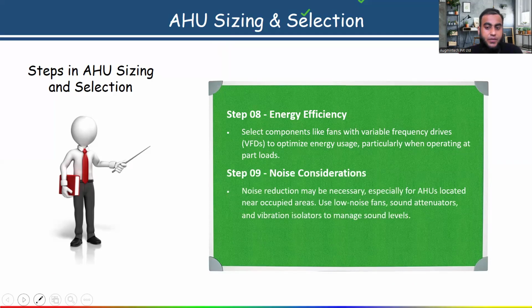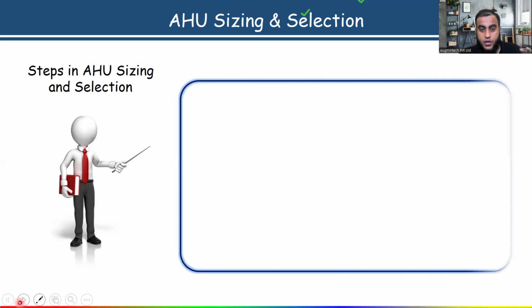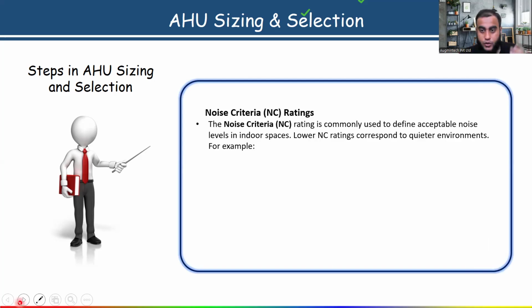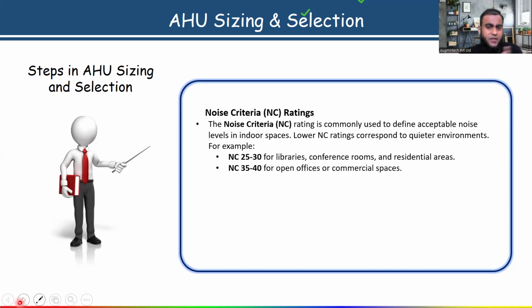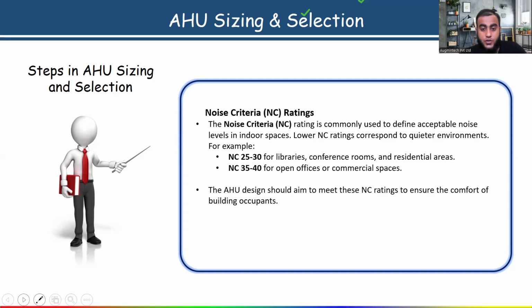Noise reduction may be necessary, especially for an AHU located near occupied areas. So use a low noise fan, sound attenuator, and vibration isolator to manage the sound level. Here you can see the noise criteria rating is given. The noise criteria rating is commonly used to define acceptable noise levels in indoor spaces. Lower noise criteria ratings correspond to a quieter environment. For example, 25 to 30 decibels for libraries, conference rooms, and residential areas. Between 35 and 40 decibels for open offices or commercial spaces, you can go up to 40, and the maximum you can go is 45. The AHU design should aim to meet this noise criteria rating to ensure the comfort of building occupants.